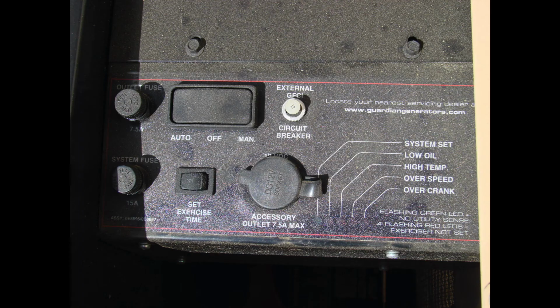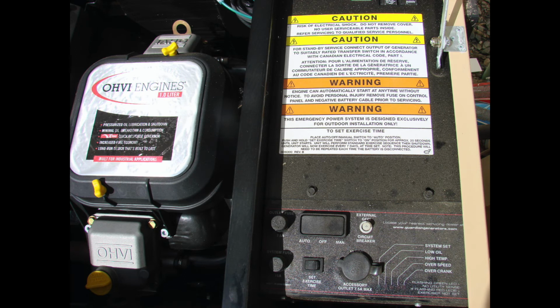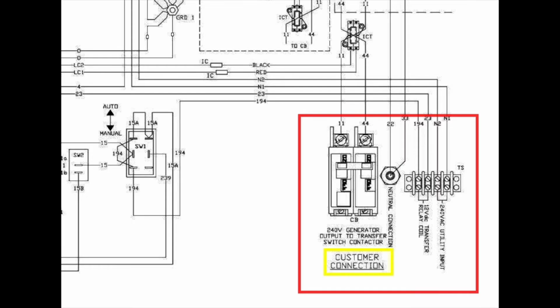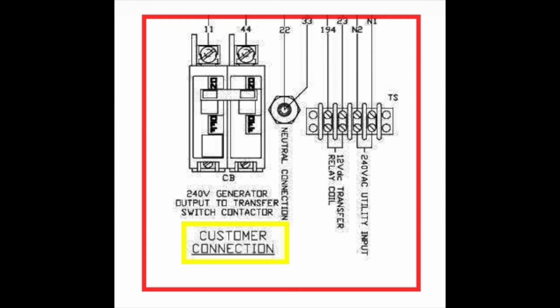This is for the larger generators that are well above 5 kW. In this case, again, it's typically for 13 to 16 kW on up. And the enclosure opens up, and with your generator, of course, you're going to get your installation manual. You'll notice that the biggest thing for you to really pay attention to here is the circuit breaker, where the generator output feed will be attached, and that is the circuit breaker protection for the generator.